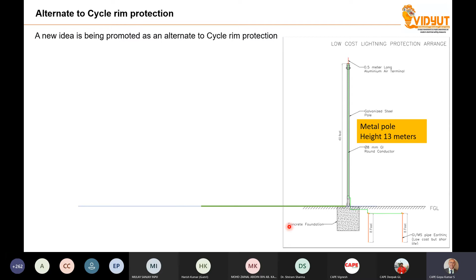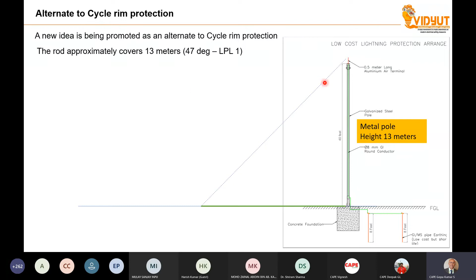Now you read the earthing system: GI MS pipe earthing, low cost but short life. So that means after 2 years, the earthing is gone. Will it work? Let us analyze. This rod, as per the theory shown in the previous slide, if we take level 1 protection, protects up to a 13-meter pole, 47 degrees. So what I am showing in this dotted line is approximately the area which is protected.